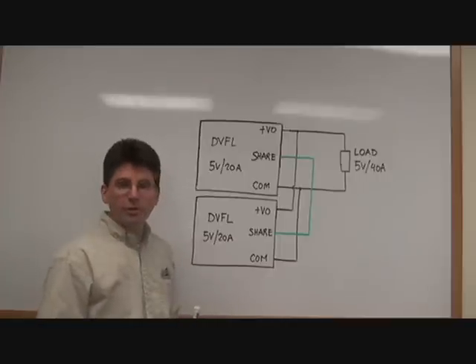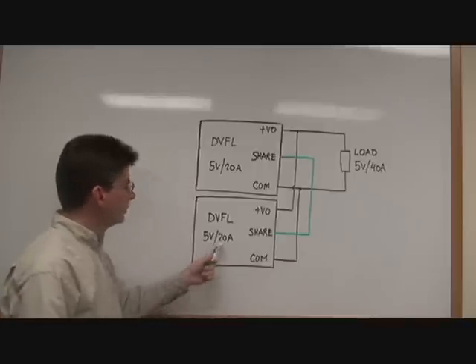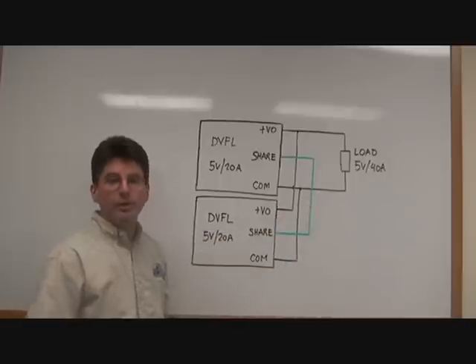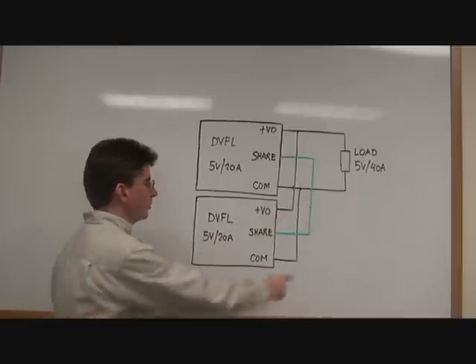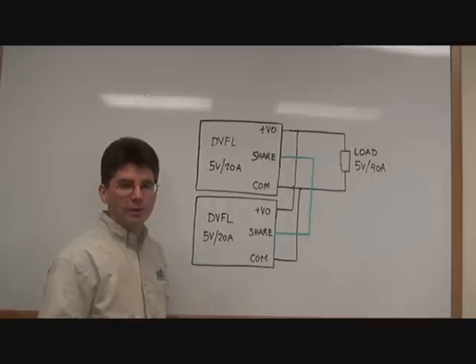They will also function as one converter. So in this example, each converter is 5 volts at 20 amps. The load requires 5 volts at 40 amps. So this combination of two converters will function as one DC-DC converter.